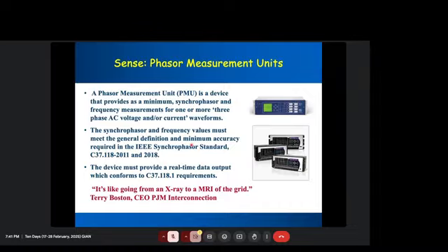How does the GPS signal get converted? What is the PLL, the phase lock loop? Why is it needed? How is the filtering done? You can talk about a lot of different things, but the essence here is that it takes the analog input, which is CT and PT, and gives you digital output, which is the phasor measurement, with voltage magnitude, with angle, with frequency, in a standard format, which is 37.118, and in real time, meaning it can report fast enough. Some PMUs report 200 times per second, and some report 30 or 60 times per second.